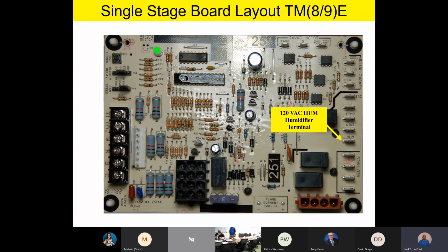Right below that, we have a HUM terminal. That's for a humidifier output, and that's a 120 volt output for a humidifier. Now, it should be noted that it's an isolated relay output, 120 volt output. And the neat thing about that is anytime you have a heating call, you can take that 120 volt output and utilize it for powering up a humidifier.